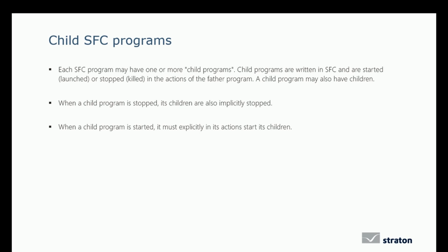The child program. Each SFC program may have one or more child programs. A child program is written in SFC and is started or stopped in the actions of its father program. A child program may also have its own children. When a child program is stopped, its children are also implicitly stopped. But when a child program is started, it must explicitly in its action start its own children.